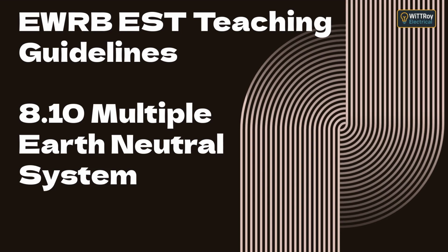Summary. Let's summarize Topic 8.10, Multiple Earth Neutral System. We covered how the MEN system is configured, why the neutral is earthed at multiple points, the main purposes of the MEN system, the need for reliable low-resistance earth paths, the danger of high resistance or missing MEN links, and how distribution systems must be properly connected downstream. The key takeaway is the MEN system keeps touch voltages low, allows quick disconnection of faults, and forms the backbone of safe electrical systems in New Zealand. That concludes Topic 8.10, Multiple Earth Neutral System. In our next lesson, we'll move on to Topic 8.11, Protection, where we'll look more closely at fuses, circuit breakers, and overload devices that protect circuits and equipment from excess current.